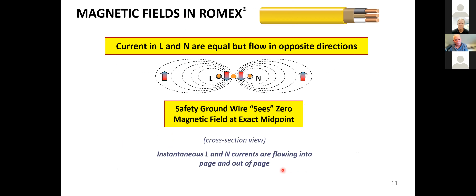So I did a controlled experiment where I had conduit and I strategically placed conductors at specific distances apart. You can see it in the paper. And you can see here the difference between the same wires in the same positions and the same current with and without conduit. In this case, it was EMT, kind of a thin wall steel stuff.